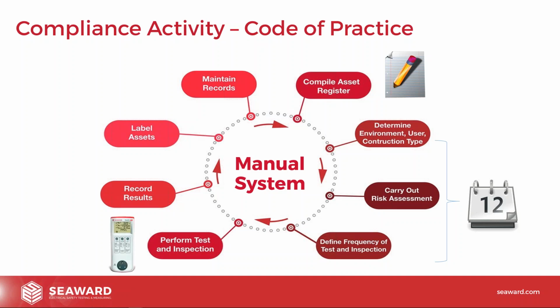Then we perform the inspection and testing. So you're generally using one of our simple PAT testers, something like a Prime Test 100 maybe, or a Prime Test 250, which gives you very basic functions. They do actually have automated sequences in there. So when you press test for class 1, it will go through earth continuity, insulation and leakage. So they will go through an automated sequence and give you the pass-fail results from there.